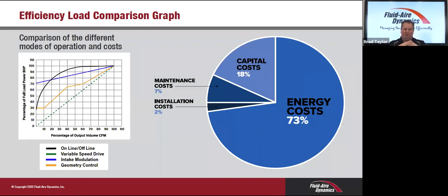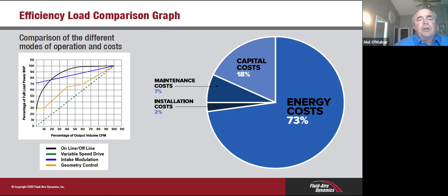There is a bit of a curve to it, but for the sake of this presentation, that's the line that it tends to trend. Anything on this, Laura? Or, go on, Mel. Well, Brad, from your chart, I think most people can see with your percentage of output at, let's say, 20%, you go up to the purple line with the modulation, you see how much power savings there is. And if you go from the green dotted line, which is your variable speed, to the purple, there's huge amounts, especially at low demands.